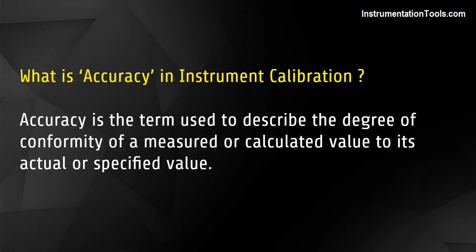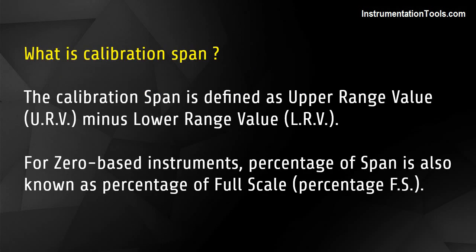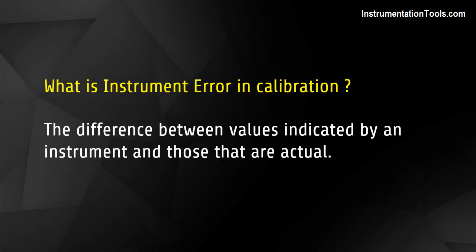What is accuracy in instrument calibration? Accuracy is the term used to describe the degree of conformity of a measured or calculated value to its actual or specified value. What is calibration span? The calibration span is defined as upper range value (URV) minus lower range value (LRV). For zero-based instruments, percentage of span is also known as percentage of full scale (%FS). What is instrument error in calibration? It is the difference between values indicated by an instrument and those that are actual.